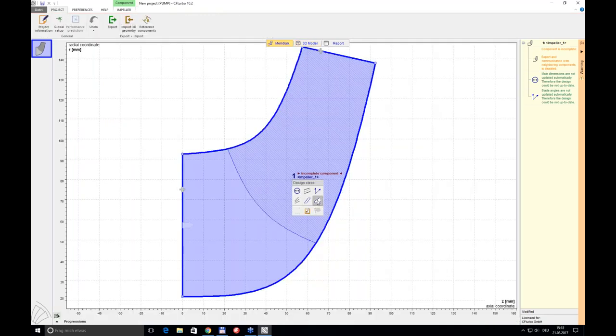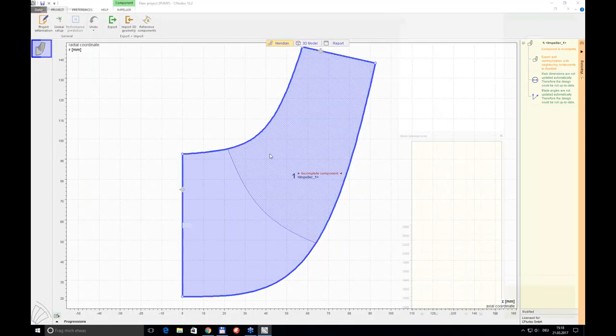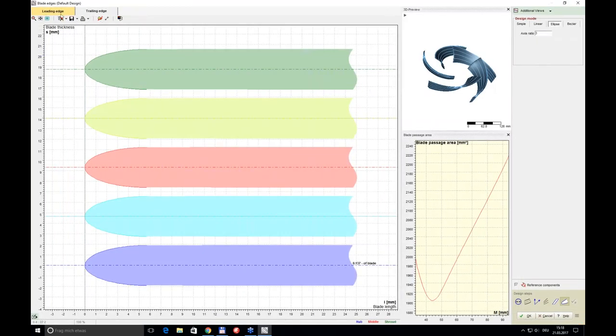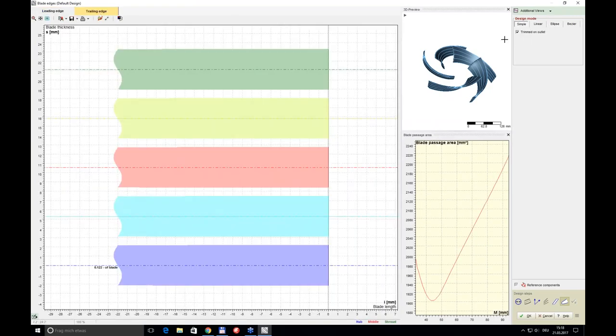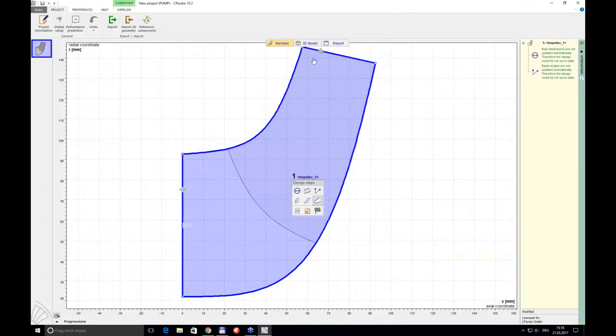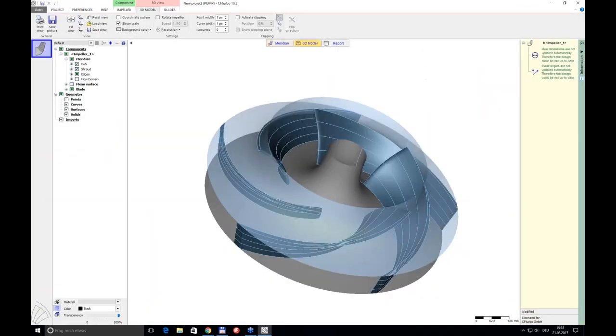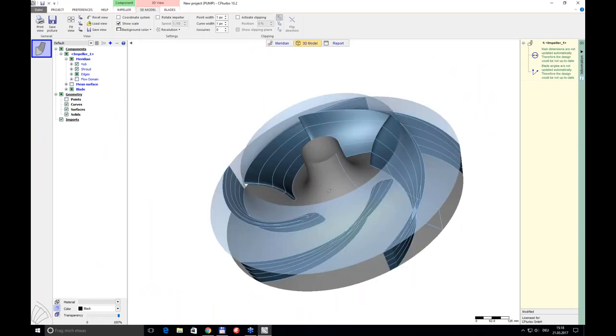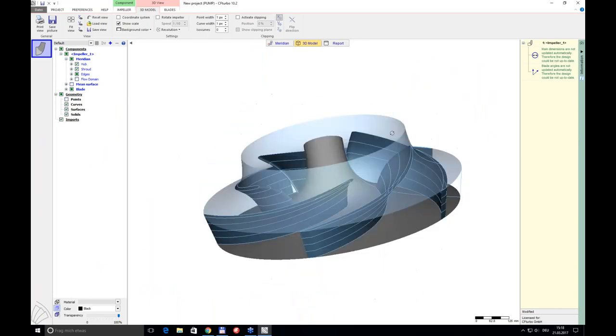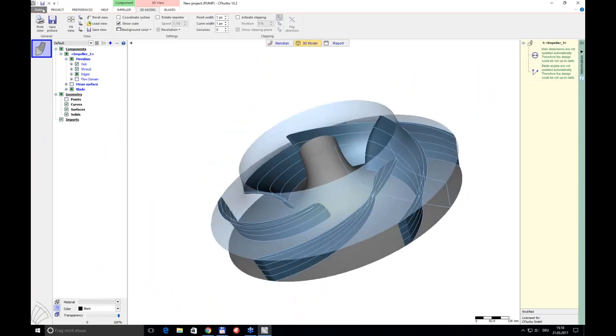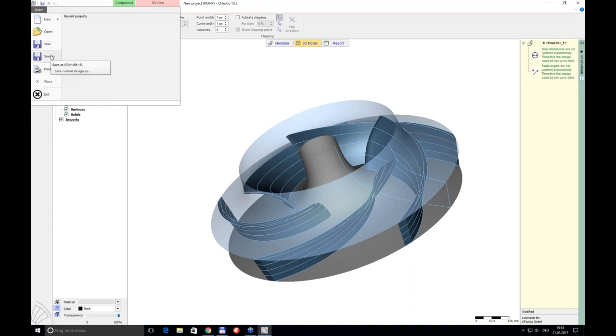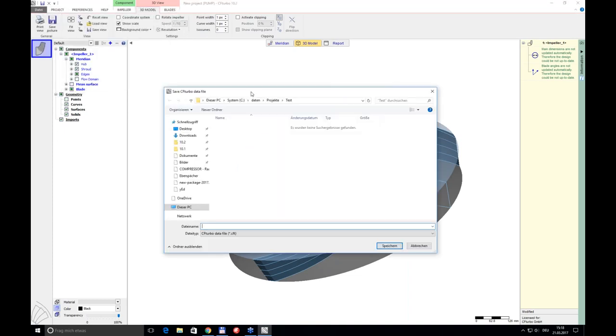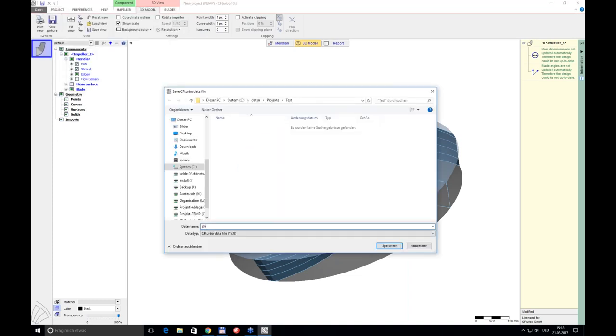After applying linear thickness the 3D model shows blades with very sharp edges. The last design step shapes the leading and trailing edges: the leading edge can have an elliptic shape and the trailing edge is typically trimmed at the outlet. With that done, the first initial design of the impeller is complete. I save it and call it pump one.